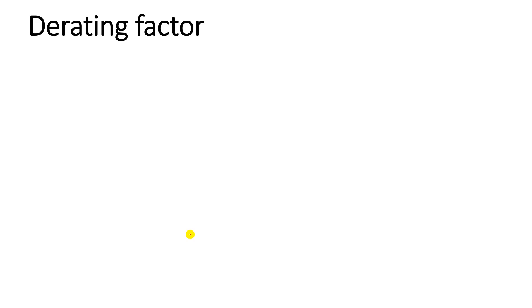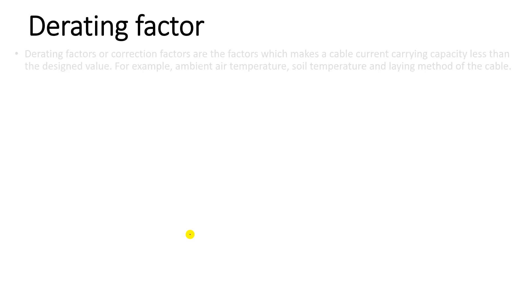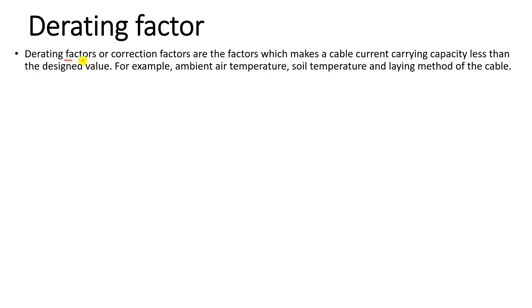In this lesson we discuss the derating factor in cables, specifically due to cable formation in the trefoil and flat formation. Derating factors, or correction factors, are the factors which reduce a cable's current carrying capacity below its designed value. Several conditions such as ambient air temperature, soil temperature if buried underground, and the laying method or cable formation can all lead to derating.